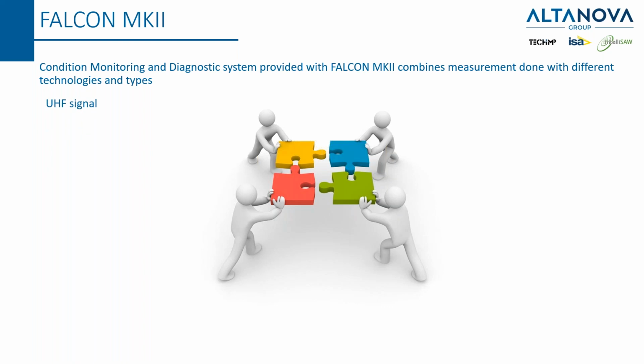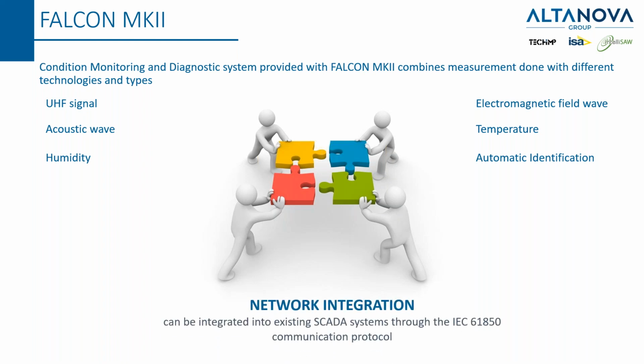In fact, the Falcon Mark II can get a signal from UHF, from electromagnetic field waves, from acoustic waves, and can also have humidity measurement and temperature measurement. It also has the automatic identification as for the Falcon Mark I. And it's important to note that, like the Falcon, it has communication facilities like network integration using IEC 61850.